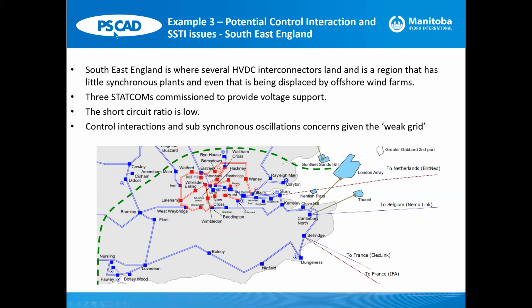There was a problem with voltage levels in this region, and the utility was looking at installing 3 STATCOMs at Bolney, Ninfield, and another one in nearby proximity. They wanted to see if the STATCOMs would interact with the synchronous machines and the power electronics from offshore. These types of studies are done in PSCAD or EMT programs. It's essential to perform such studies to look at control interaction and subsynchronous oscillations in weak grid conditions.